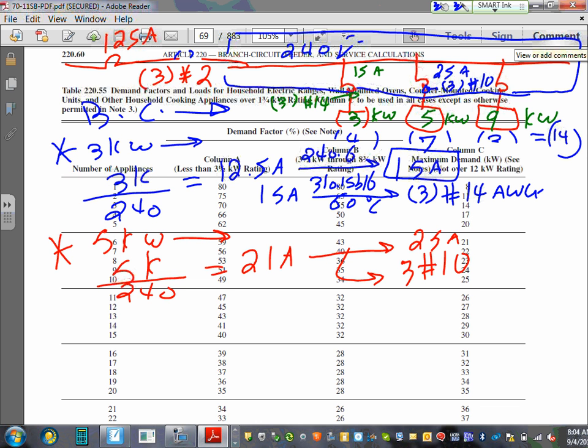Number 10. Number 14. Remember what we said, number 14, you shall not put an overcurrent protection device more than 15 amps. Number 12, you can't put an overcurrent protection device on number 12 more than 20. Number 10, you can't put an overcurrent protection device more than 30. So why do I have to go to 10 here, not 12? Because look at my overcurrent protection device, my circuit breaker is 25. By the way, what we're sizing are these conductors. These are what we size.